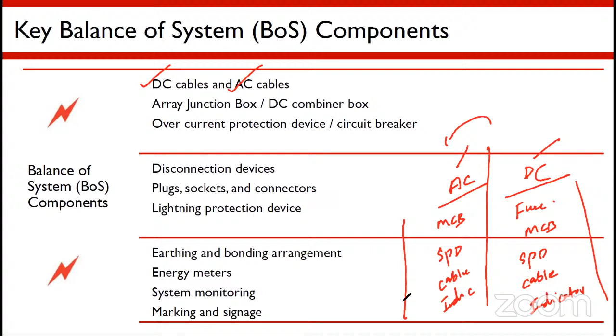The next component is the array junction box or combiner box. This junction box or combiner box is mainly on the DC side. If you see the SLD of a plant, I can show you right now on the whiteboard. So you can take this as an example - this is your PV array. From the PV array, the source is the sun.